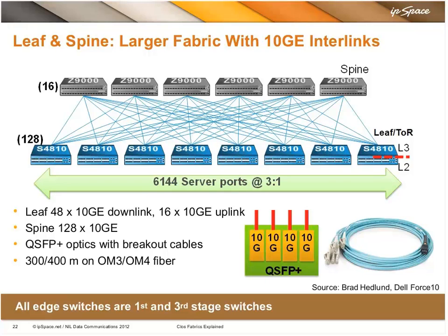Each parallel lane of 10 gig is going to be its own interface on the switch, available as an IP routed path for ECMP to make a hashing decision and place flows on any one of those four 10 gig lanes. When I have four QSFP optics plugged into the switch for the uplink, four times four equals 16 — so now there are 16 logical ports of 10 gig going to the spine layer.